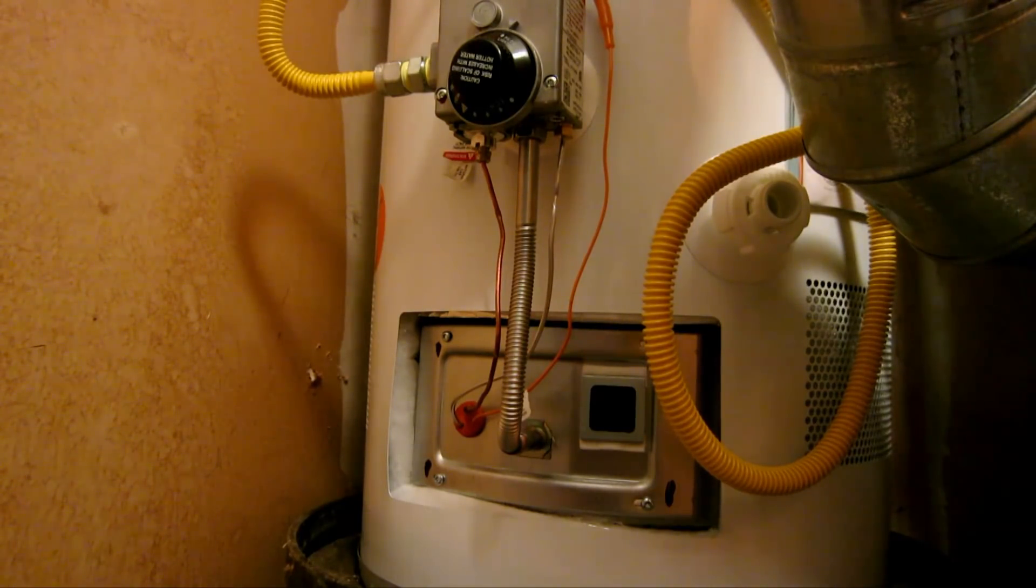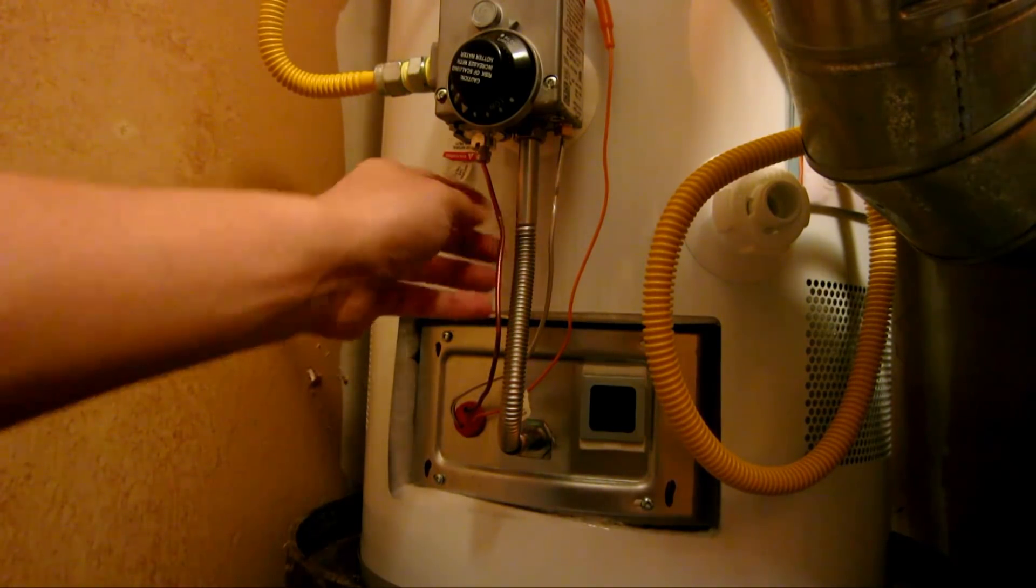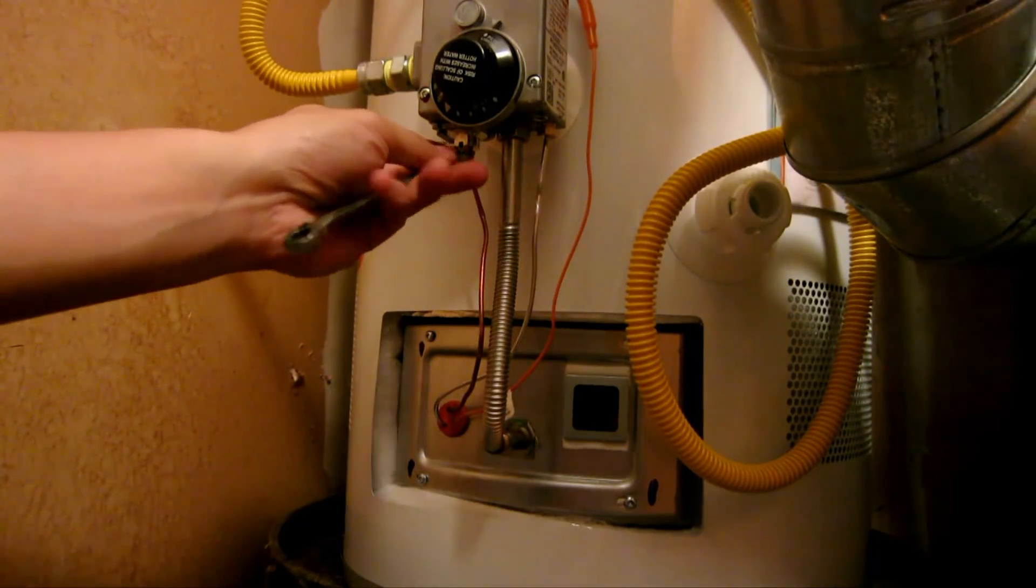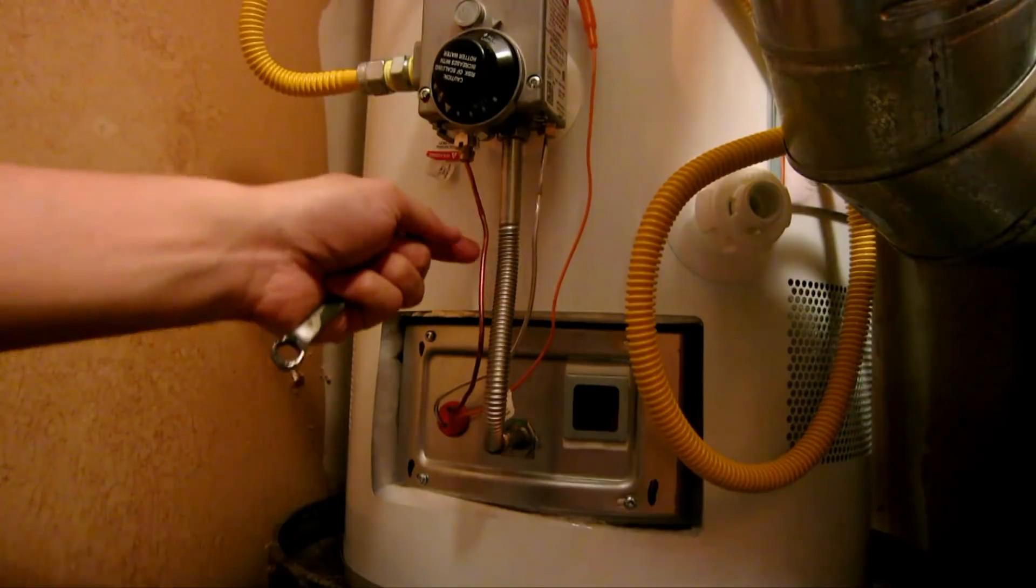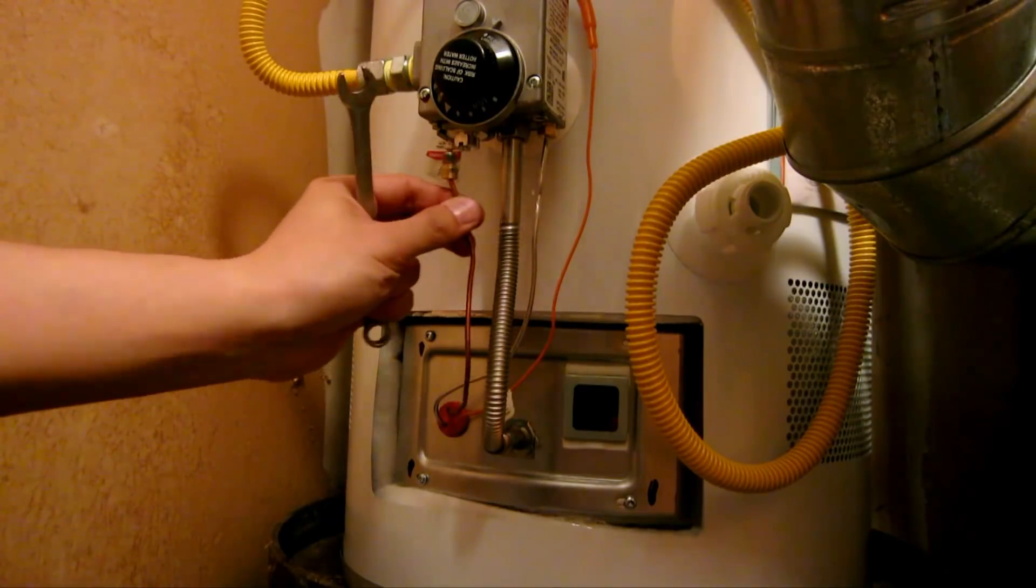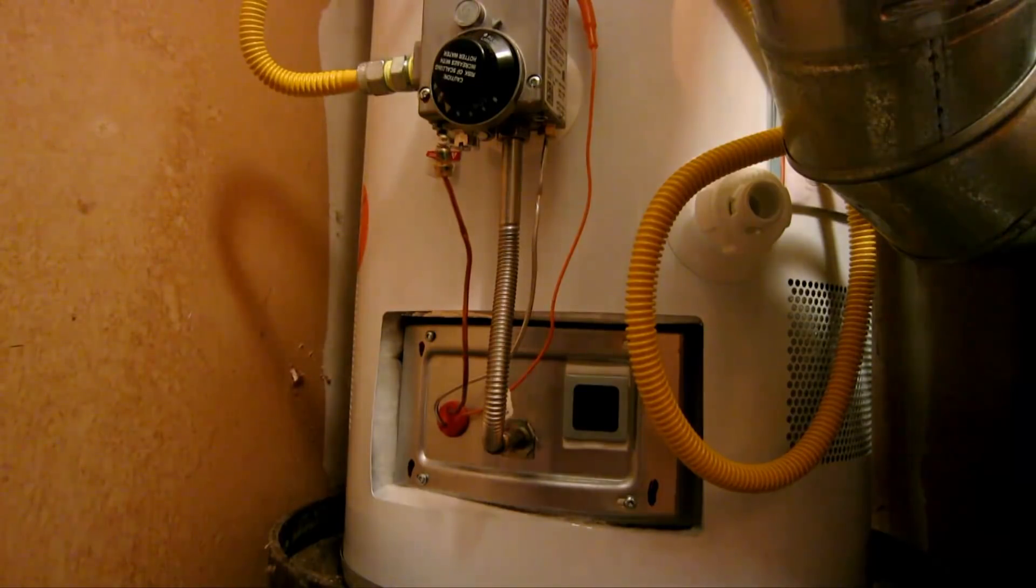So, I'm going to do some quick diagnostics to see what's going on. The very first thing I want to figure out is if this thermocoupler is working. What I'm going to do is I'm going to disconnect the thermocoupler. It's this copper wire right here, and it slides out just like that. So, that's a thermocoupler.